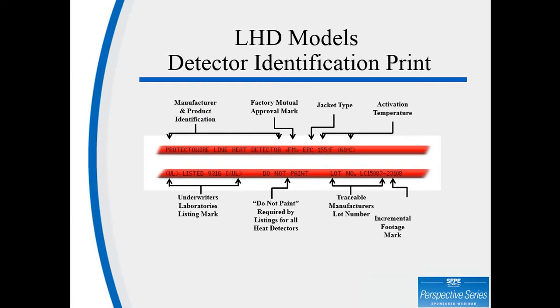The system designer has to be able to identify, and the installer has to be able to identify, the product that he's working with, or the LHD type or model. So you'll see that on the LHD you have these markings: the manufacturer product identification, the Factory Mutual approval mark, the jacket type, in this case EPC, which is a PVC jacket, and the activation temperature in Fahrenheit and also in Celsius. On the second line we have the Underwriters Laboratories listing mark and category, do not paint required by listings for all heat detectors, the traceable manufacturer's lot number, and the incremental footage mark.